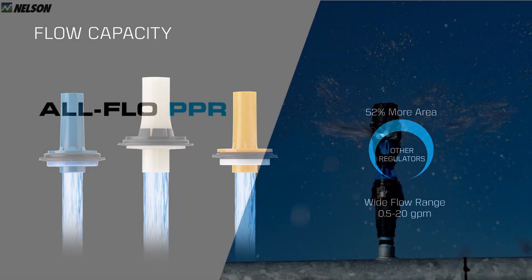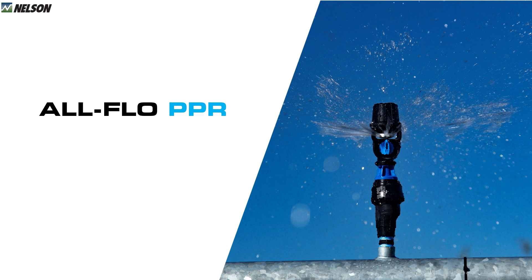All these features combine to make an efficient and accurate regulator that will also save energy. Pressure is your friend at the sprinkler but your enemy at the pump, so anything you can do to reduce pumping costs is significant. The All-Flo requires a minimum of five PSI over the nominal pressure to maintain accurate pressure, compared to seven PSI for other regulators. Depending on operating hours, system flow, and local power costs, this could save you about fifty dollars per year per PSI on a standard quarter-mile machine.